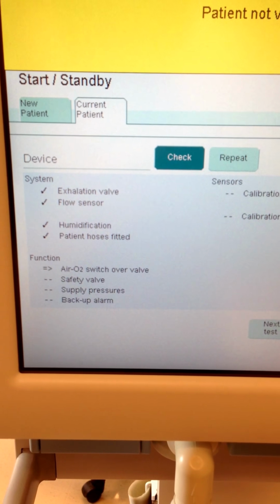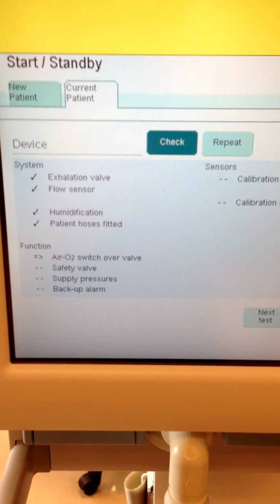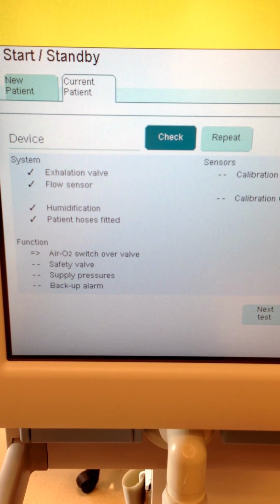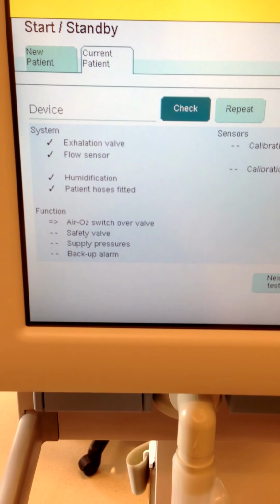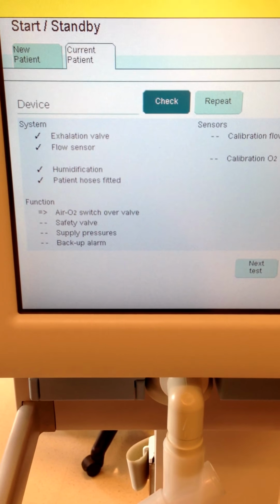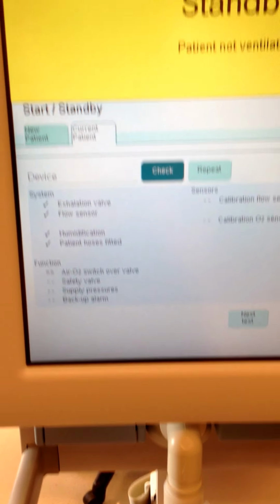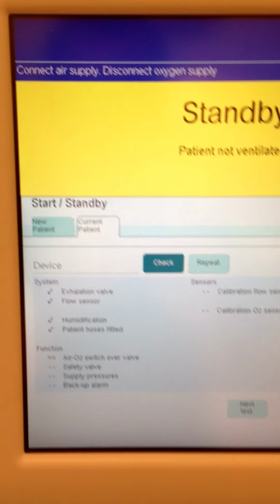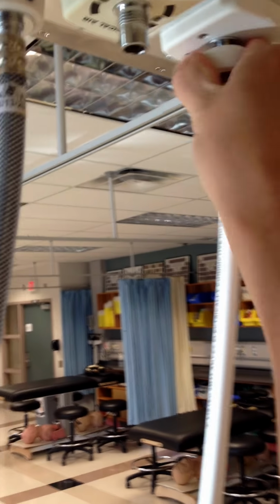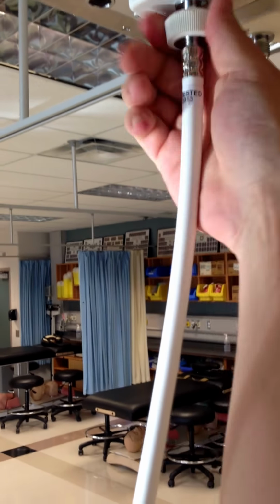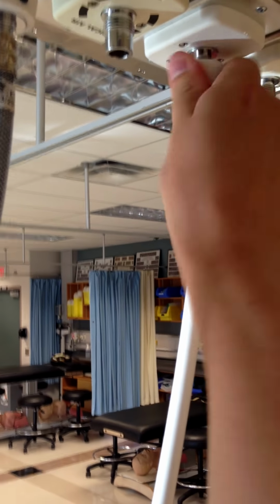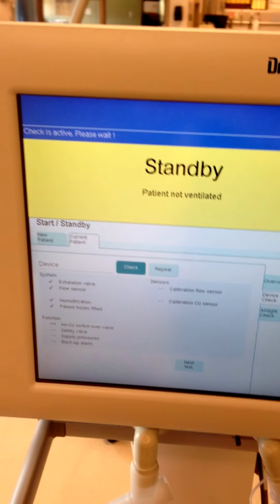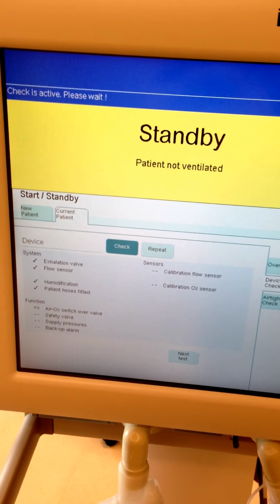Now it's going to go through the function test of the device to make sure that it's safe to use for our patient. There's no problems with the switchovers or any of the valves and internal pressure systems. Connect the air supply and disconnect the oxygen. So here's a little manual labor for you now. You come up here, unscrew your 50 psi DISS O2. It should sense that, and just switch over to an active test.